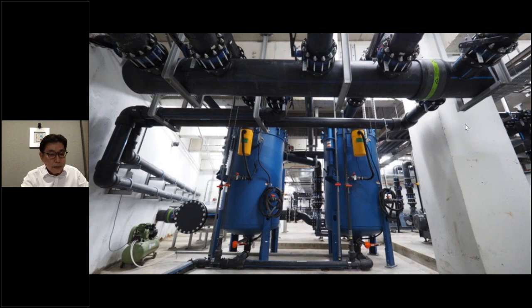Let me touch base about the maintenance in future. The issue about horizontal filters, to my experience, what Adam said is true: you need a lot of labor to remove the media, to change the media. On top of that, a horizontal filter has a lot of manifolds and a lot of valves. Then for backwashing a horizontal sand filter, you need to turn all the valves, so the filtration has to go the opposite way for backwash.